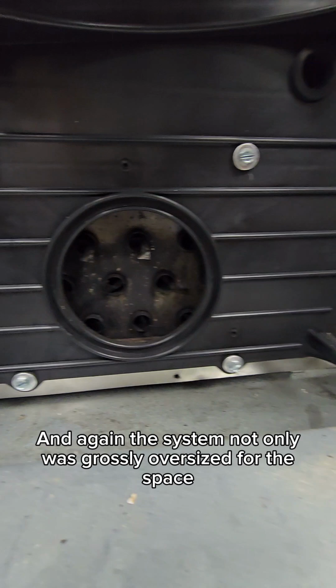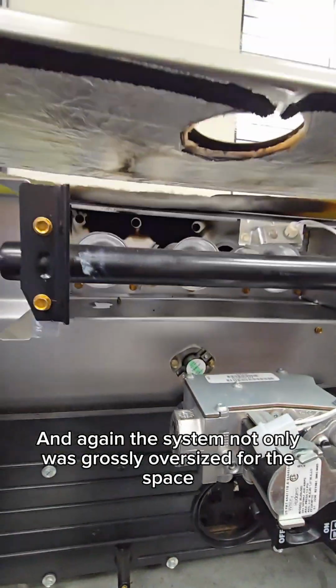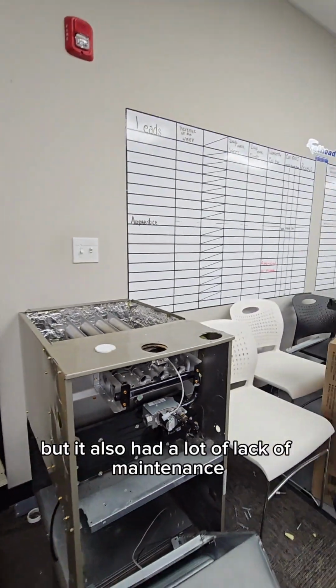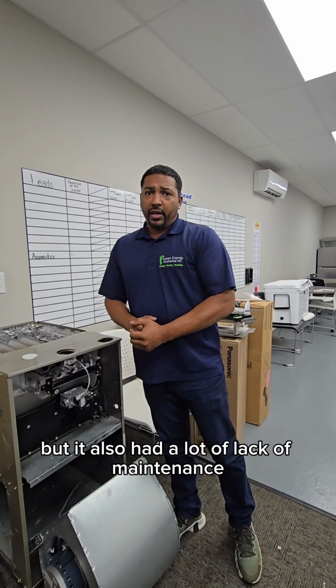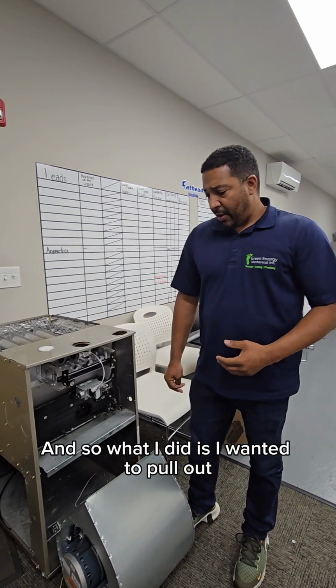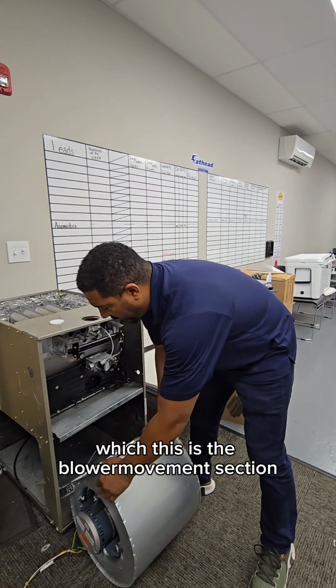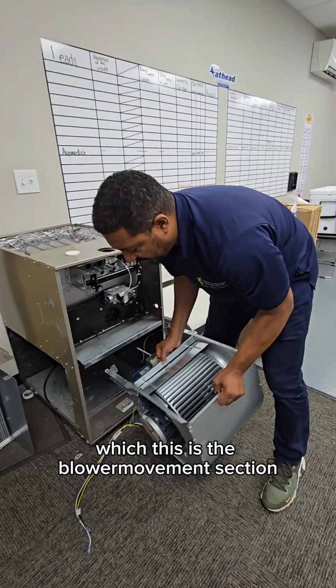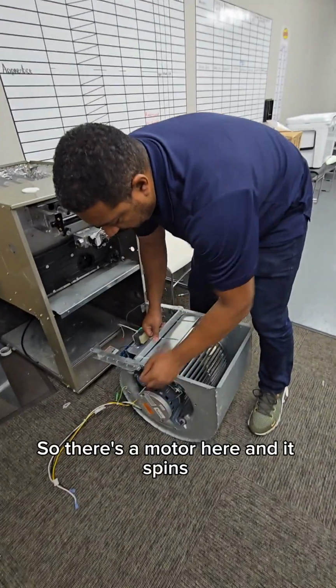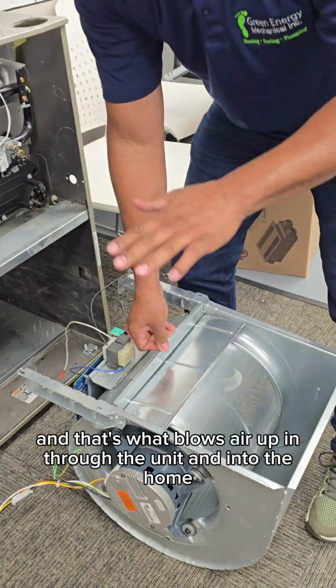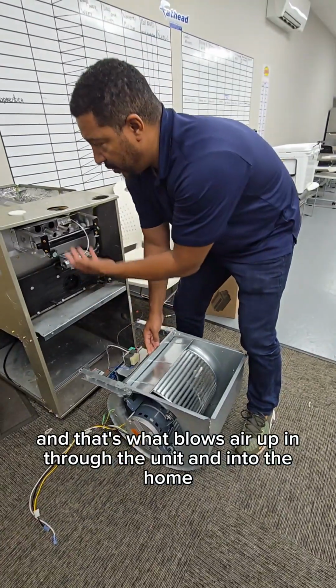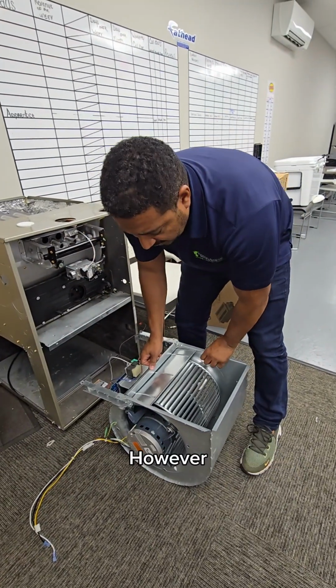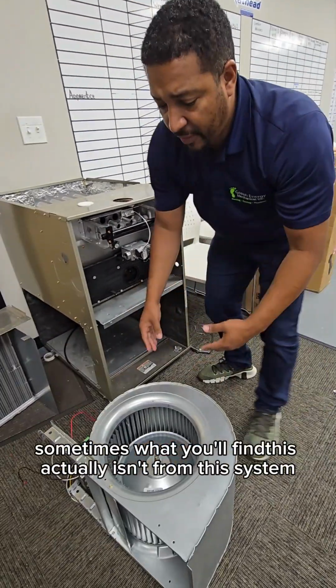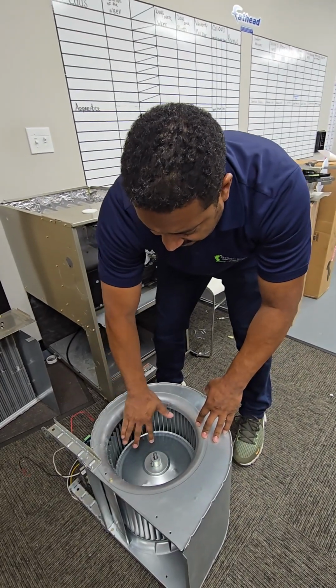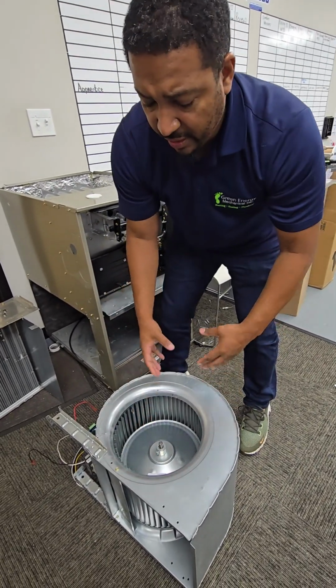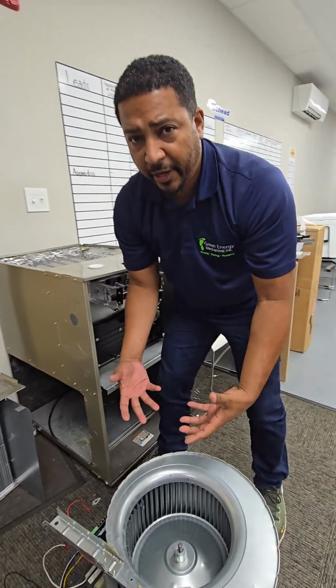Again, the system not only was grossly oversized for the space, but it also had a lot of lack of maintenance. So I wanted to pull out one of the things we find a lot, which is this blower movement section. There's a motor here and it spins this fan, and that's what blows air up through the unit and into the home. However, sometimes what you'll find, this isn't from this system, but this entire thing can be coated with just dirt and debris.